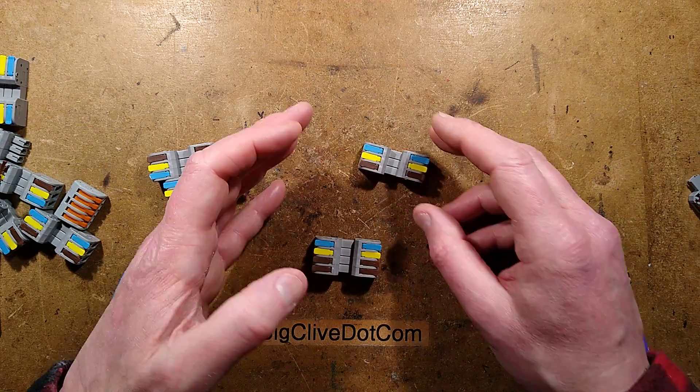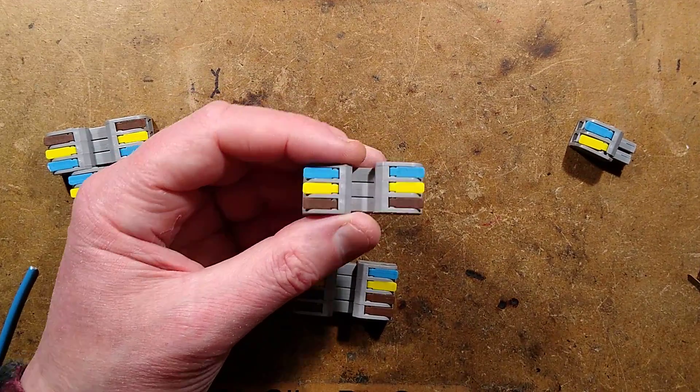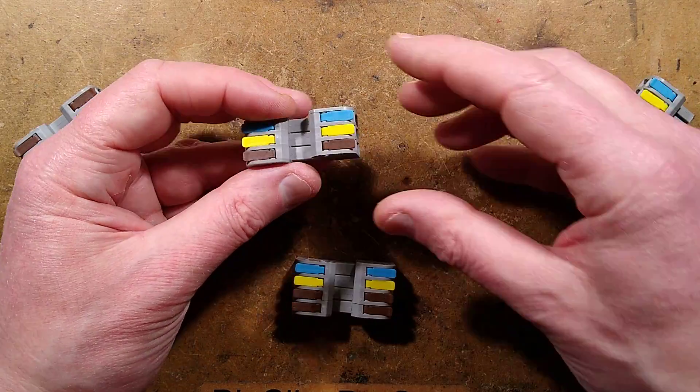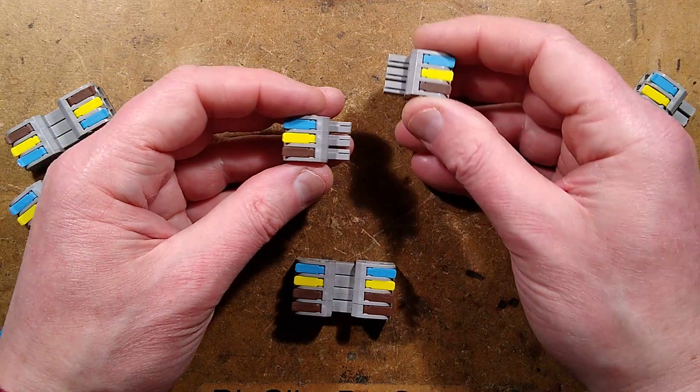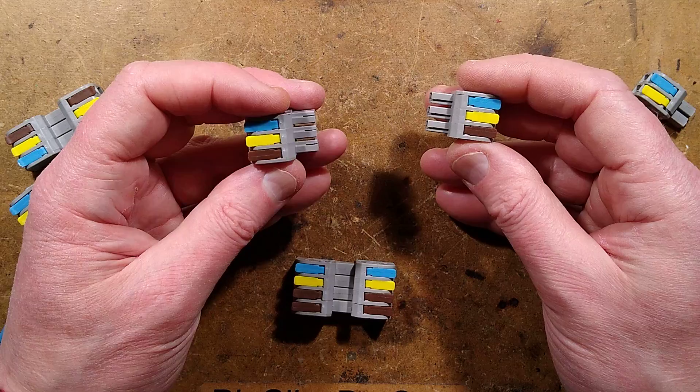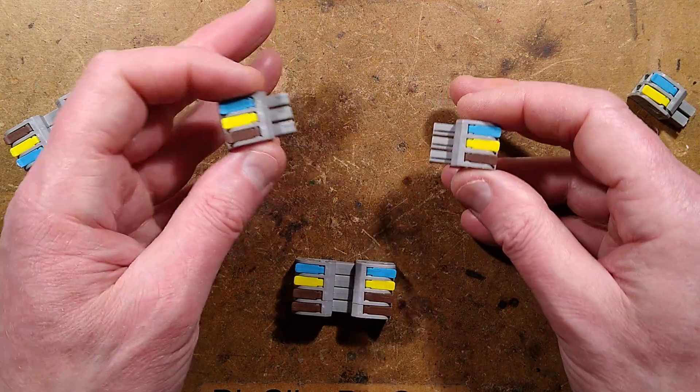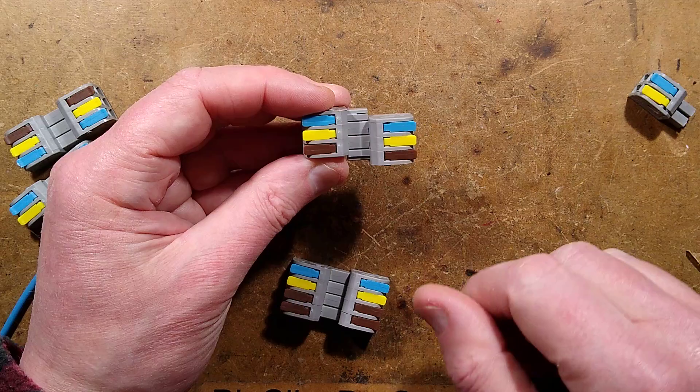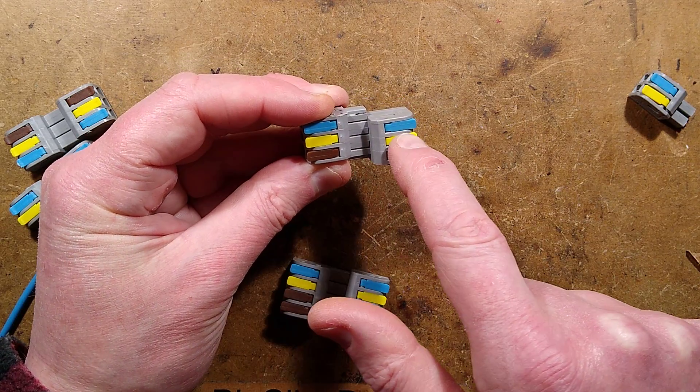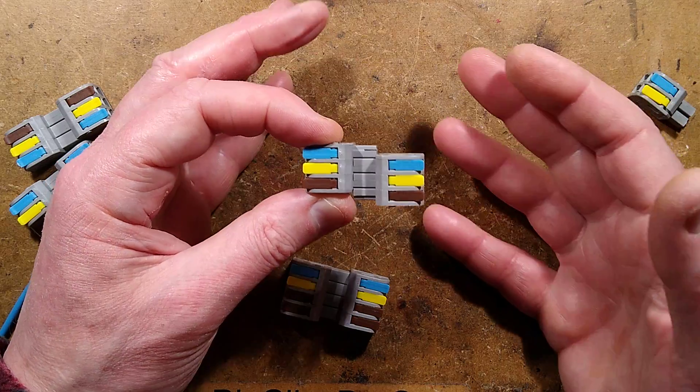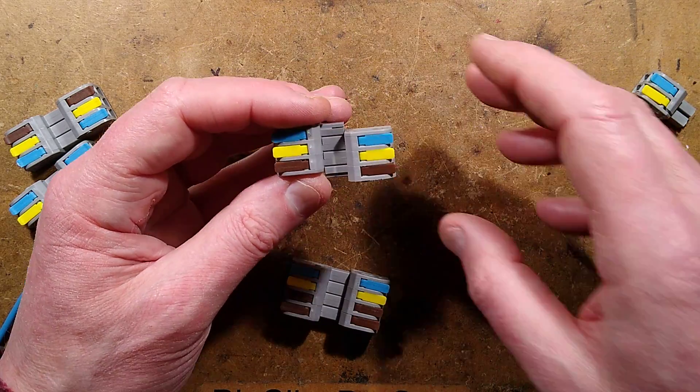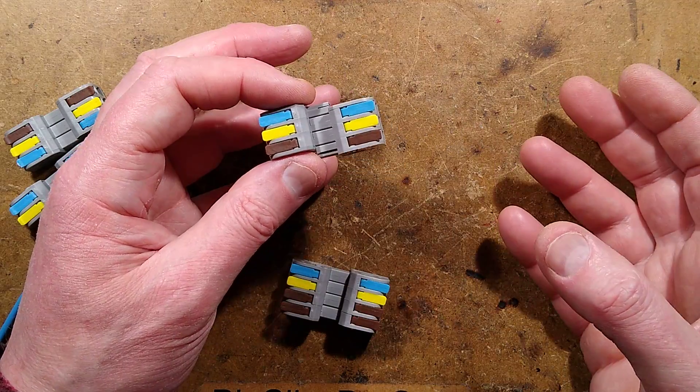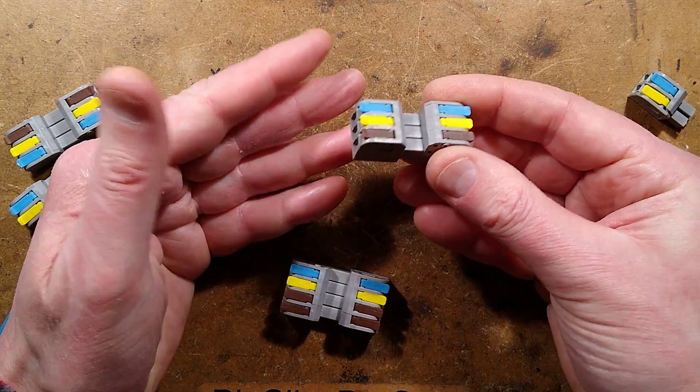If you were to use this in a machine for, say, a pump, and you had, say, a vending machine with a pump or something in it that was prone to blocking up, it would be really handy just to be able to unplug that and take the pump out and then plug it back in again. Well, there is a slight problem with these in the hands of unskilled operatives or just complacency or connectors being out of reach. Because it is a modular system, you can actually plug them in out of sync. If you did that with this exact connector as supplied, the incoming live would then go to the earth to case the pump and the case could come live with respect to the adjacent metalwork of the machine. If you had it sitting out of the machine and you wanted to just give it a quick buzz and see if it spun, that pump, when you touched it to feel that it was running, could be live. You have to keep in mind that these things can be paired incorrectly.